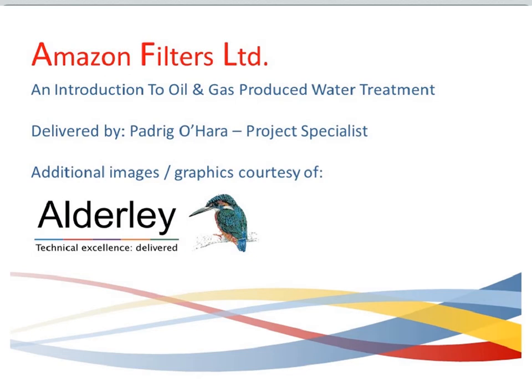Primarily, there's the external pressure that far down, which limits the practical equipment size below that of a lot of the separation technologies. There's the challenge of not being able to readily get to the seafloor to provide maintenance, which limits your technologies to those which are capable of operating effectively unmanned and without much intervention. It's an area that a lot of companies are looking at, but currently only fairly crude technologies are available, and certainly only suitable for reinjection of the water, and not able to get down to the required oil in water levels for disposal into the water at the seabed. So any water treated that way, you could only reinject, you couldn't release into the surrounding seabed.